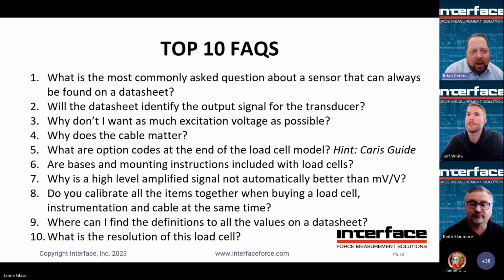So why does the cable matter? We talked about that. Cable can influence the measurement. It's going to respond to actual voltage loss as a function of length, but also perhaps more noise susceptibility. What type of cable is important? You want to use shielded. Sometimes you need to do twisted, maybe, depending on the environment. And then, what about the connector?